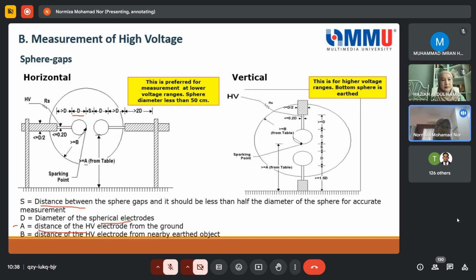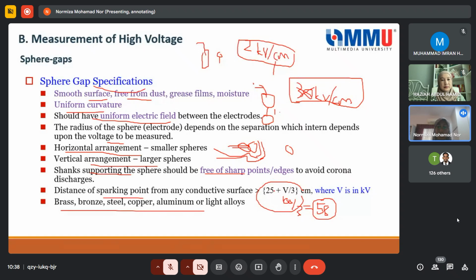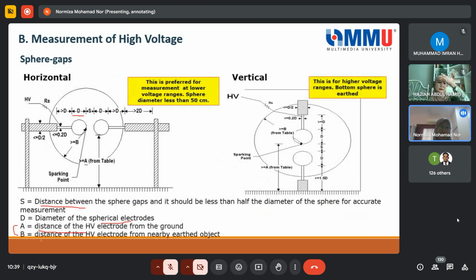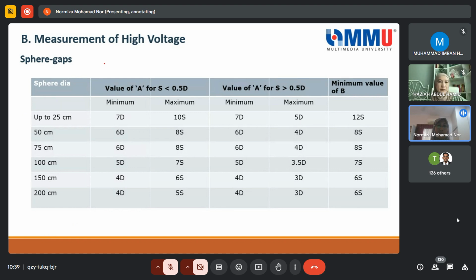So how we determine this distance, as I mentioned, you can use this one here, 25 plus V over 3. If you apply 150 kV, 150 divided by 3 is 50, plus 25 is 75 cm. The person or equipment has to be at least 75 cm away if you apply 150 kV. This is given in the standard. Of course, if you do not have a copy of the standard, you can apply that formula. But as I mentioned, different equipment would have a different safe distance, or sparking distance, as they call it.